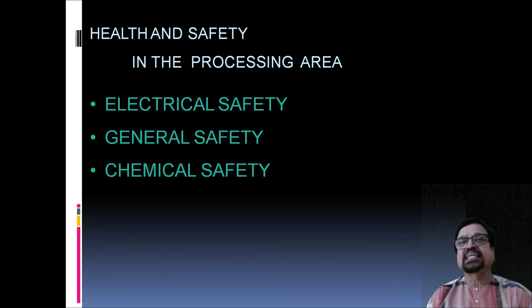Electrical safety, all the electrical equipment to be sited well away from sink and manual processing unit, because there is a risk of some water spilling over it. Then adequate earthing of all the electrical equipment, since it's a humid area, wet area. No trailing cables from the appliances. Then pull cord switches for lights. So the designing of darkroom also includes where to put the connections or switches, and which wires to put loose and which wire should not be put loose at all.